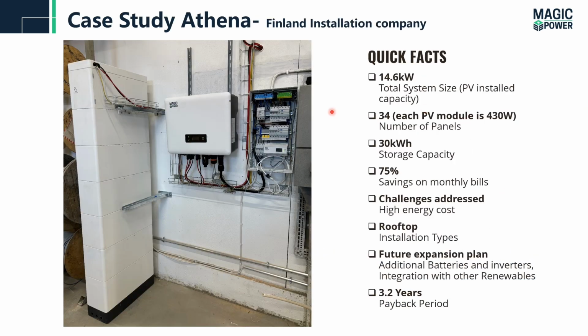So here is the case. The system is installed in Finland. The system is 15 kilowatt. The energy storage is 30 kilowatt hour. The system size for the PV is 14.6 kilowatt, where each PV module is 430 watt. For the storage capacity, there are 6 modules, each one is 5 kilowatt hour. So the total is 30 kilowatt hour.